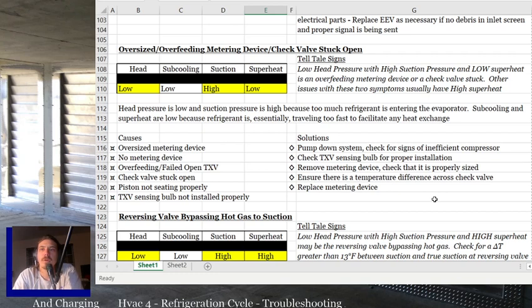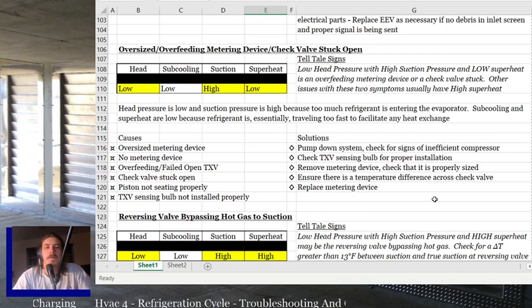Subcooling and superheat are low because refrigerant is essentially traveling too fast to facilitate any heat exchange. It's just circulating through the system super quick because there's nothing slowing it down. So it's coming out of the compressor and basically going right back to it. So you're not exchanging any heat because you're just feeding too fast. That refrigerant's moving through that system way too fast.